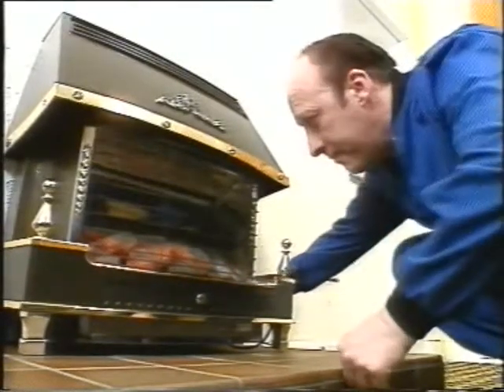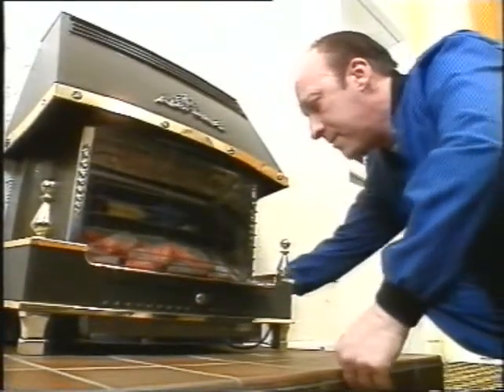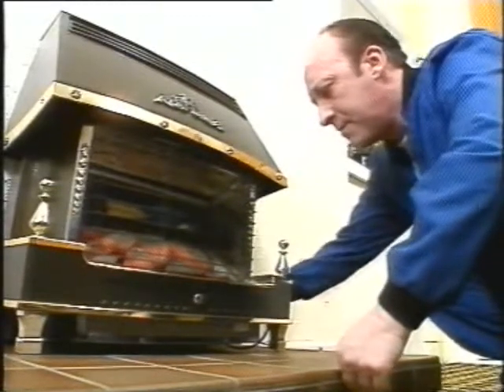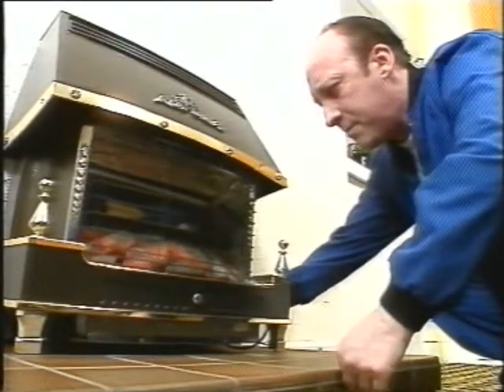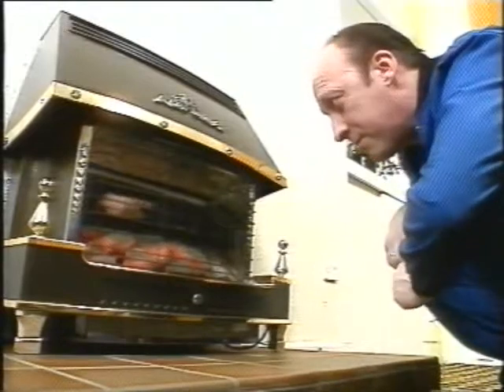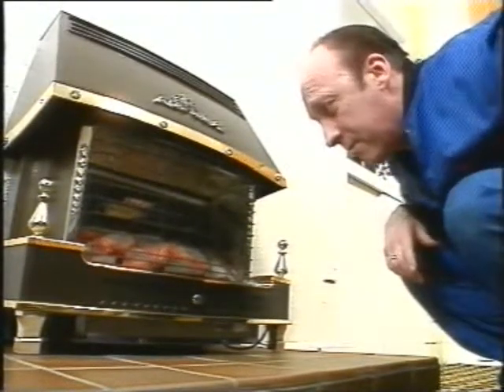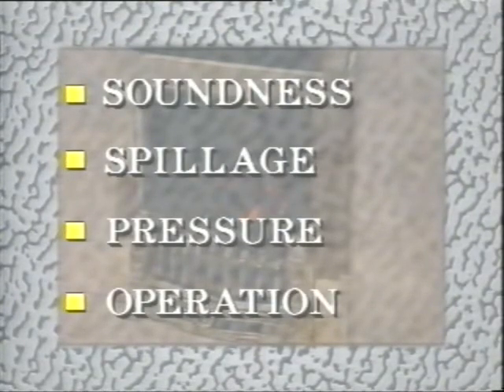With sidewall connections, there must be a gap of at least 500 millimeters between the flame or incandescent radiant source and the sidewall. Again, check the manufacturer's instructions. When you're satisfied with the installation, check for soundness and spillage. Check the burner pressure and make sure the appliance works properly.